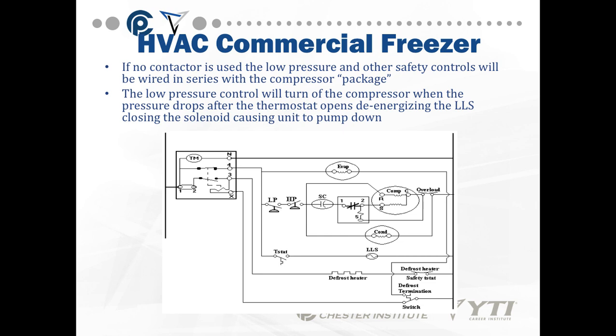If no contactor is used, the low-pressure and other safety controls will be wired in series with the compressor package. Without any contactor, all controls are wired here so that when the pressure drops and the liquid-line solenoid is closed, the low pressure will open, shutting off the condenser and compressor package.